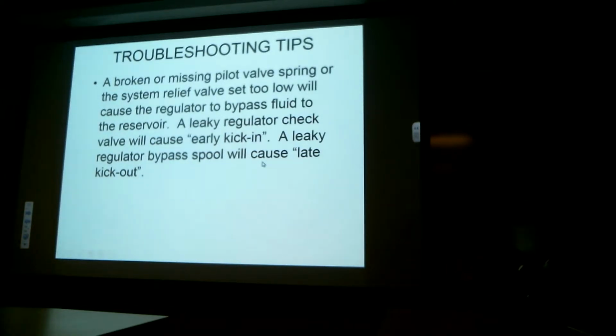There's another problem as well, and it would be late kick out. Late kick out is usually caused by a burr or an obstruction that holds the bypass spool open. When you're building up pressure, all of the fluid flow should be going into the accumulator from the pump. But if some of the fluid is bypassing the unloading valve and going back to the reservoir, it's going to take a longer period of time for you to eventually get kicked out. So that's why they call it late kick out. So you might want to remember that.